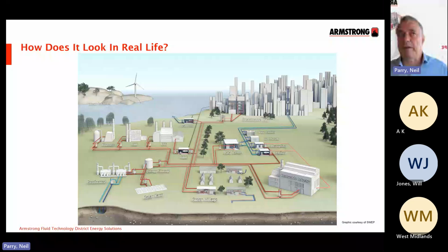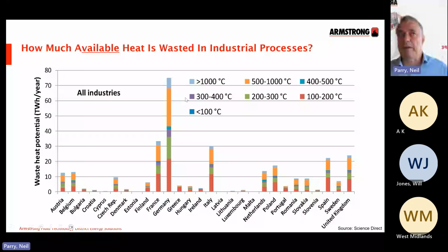But this was a report done to see what available waste heat there was in industrial processes. And you can see it's terawatt hours per year, a huge amount of energy wasted every year. And it's generally accepted that we waste around 60% of our building demand. So we could take 60% of our energy demand away if we just utilized that energy that we waste every single day. And we can see from the temperatures here, it's colored on temperature, that even the lowest temperature is still well within the realms of acceptability for a district network. So ideal to use that energy on district systems.